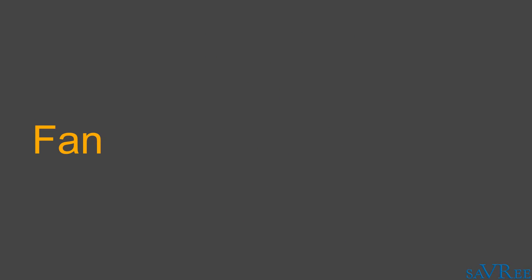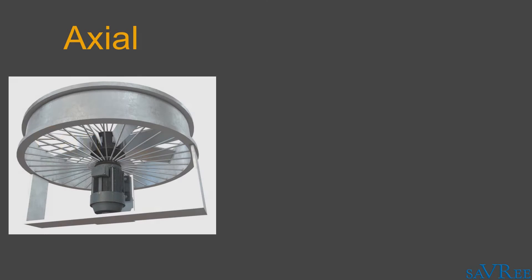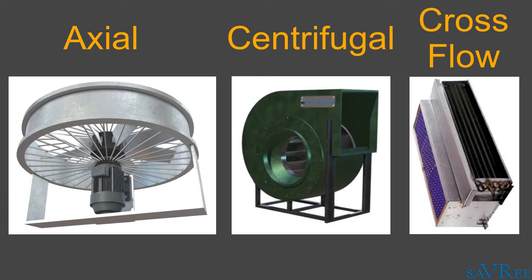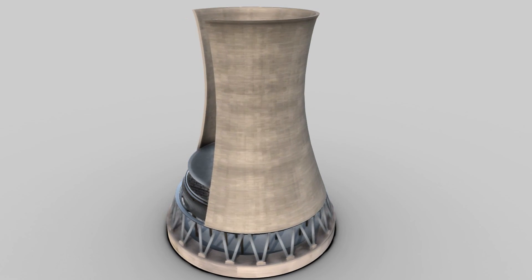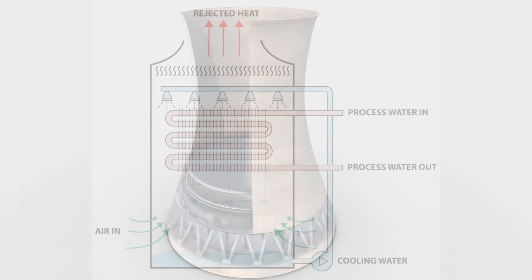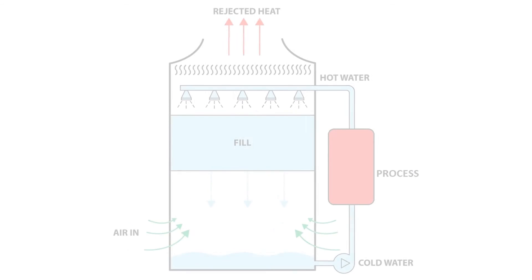Fan. Fans are used to force or induce airflow through the cooling tower and are available in several different designs. The three most common fan designs are the axial, centrifugal, and cross flow types. Fans are chosen for a particular application based on characteristics such as desired volumetric flow rate, pressure differential across the fan, and the space available. If you would like to learn more about natural, induced, or force draft cooling towers, counter and cross flow cooling towers, or direct and indirect cooling towers, check out some of the other videos available in the video description area.